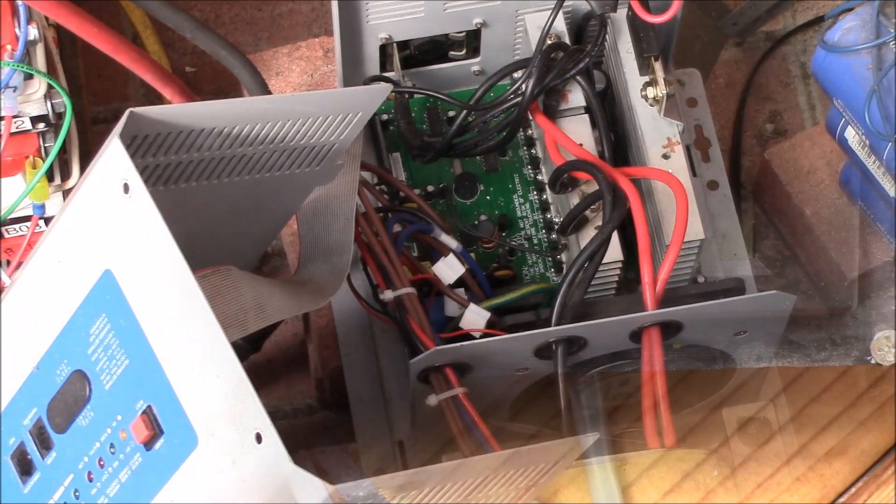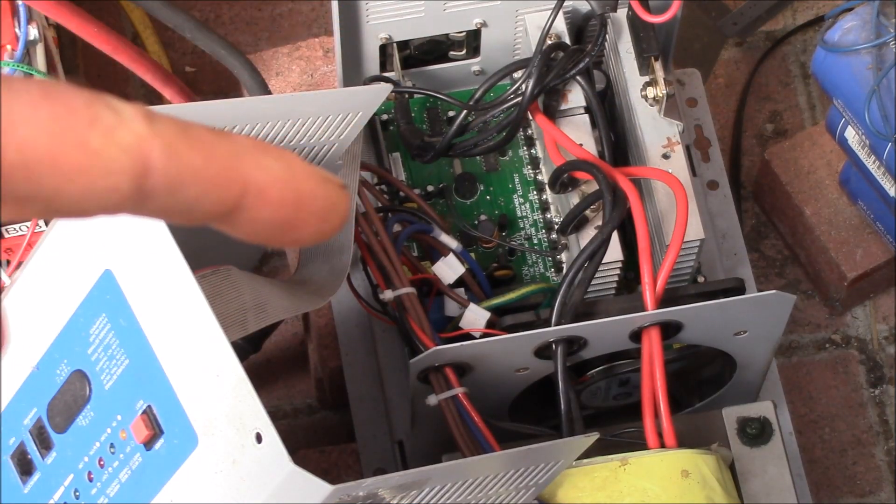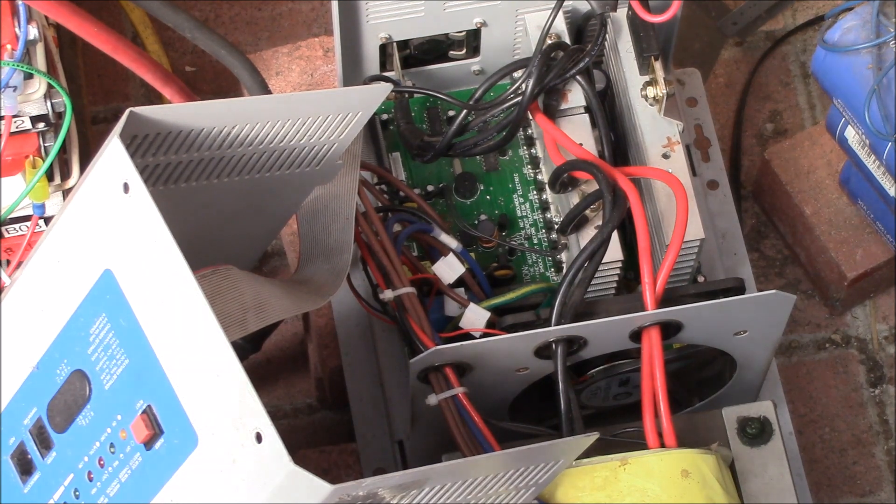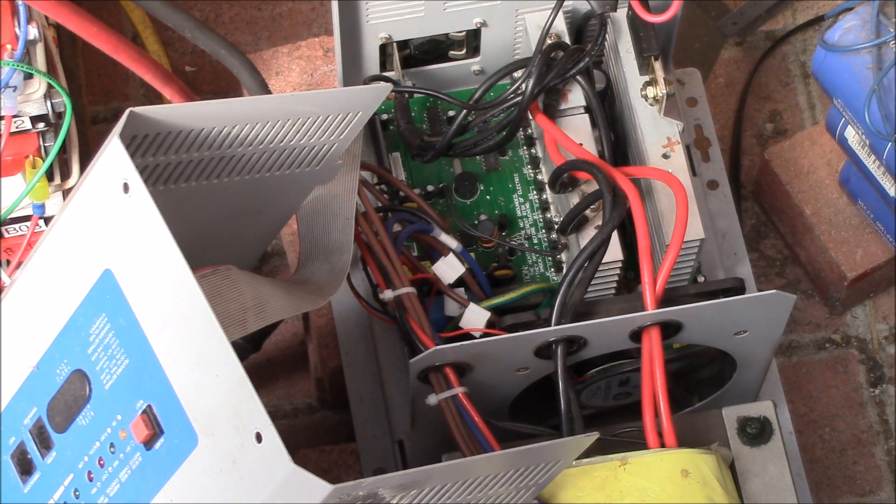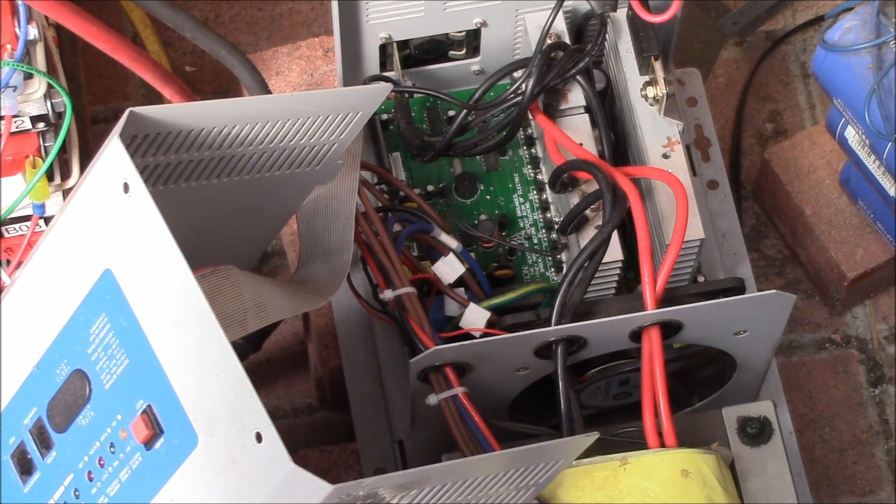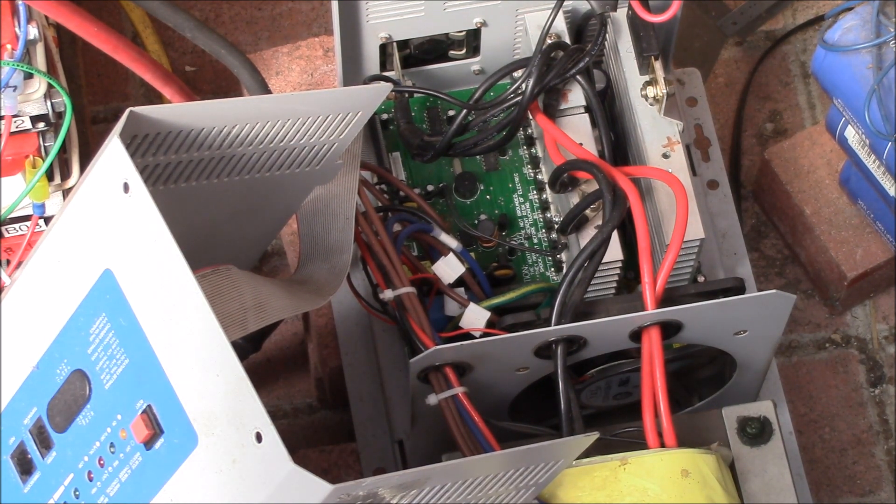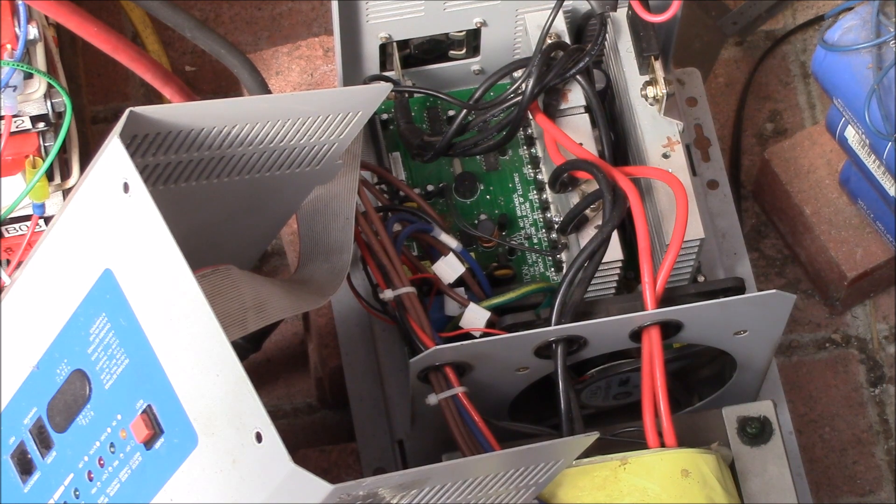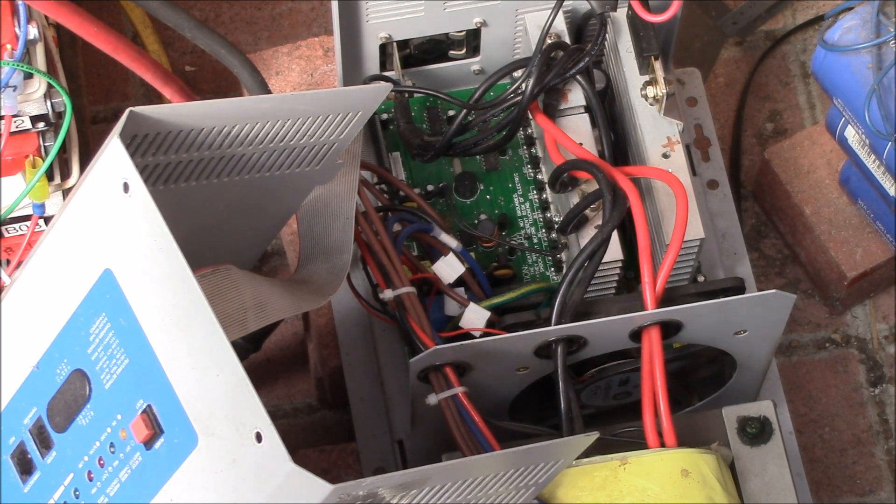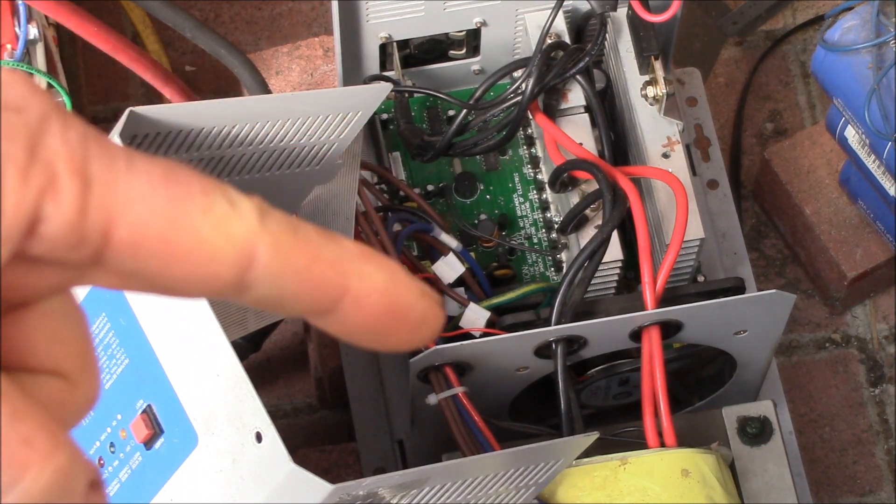So we've got the inverter working here, much quieter than it was before. There's not the really high pitched buzzing sound that was coming out when the capacitors were in the process of failing.